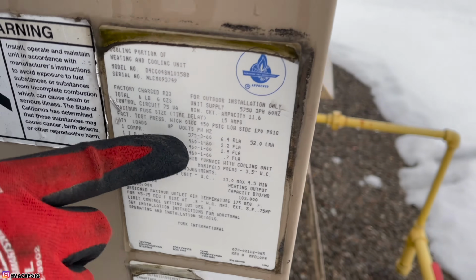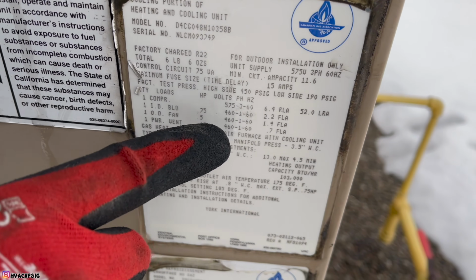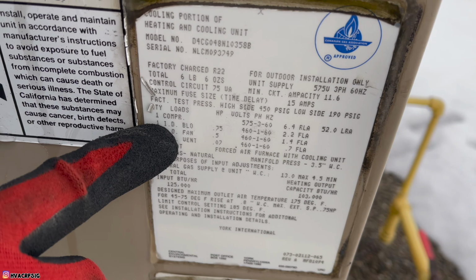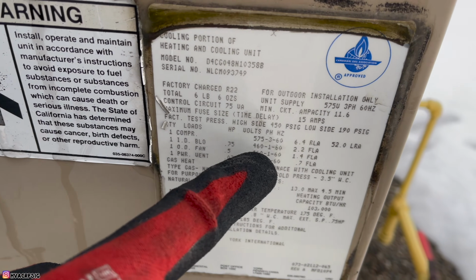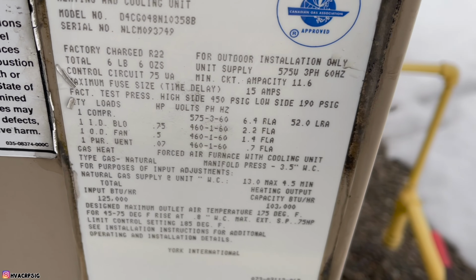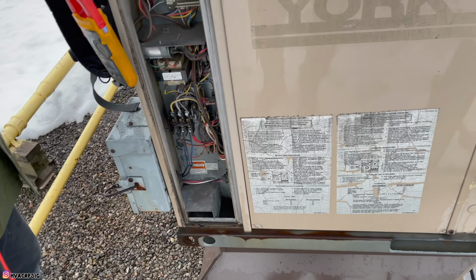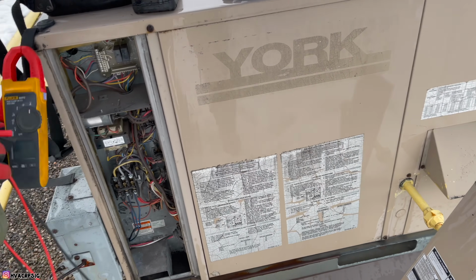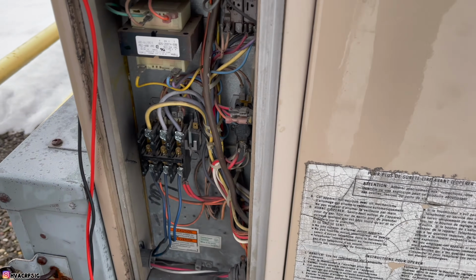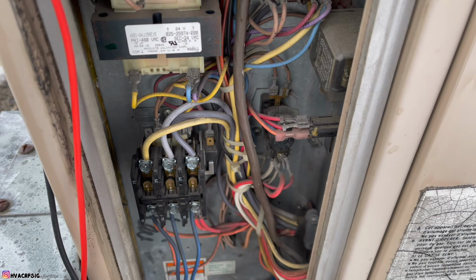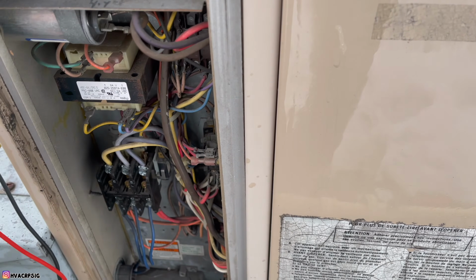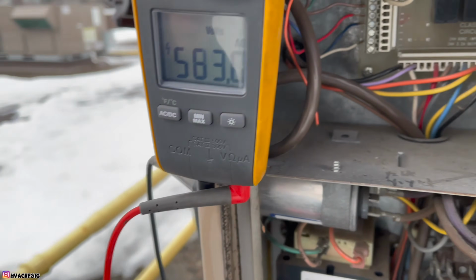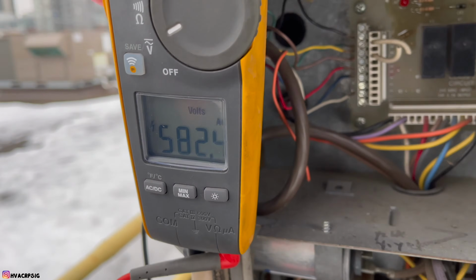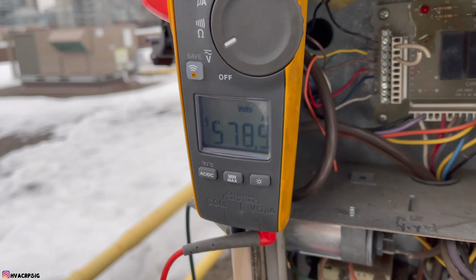Exactly. The compressor is 575 3-phase, but the motor for the indoor fan, the indoor blower, is 460 single phase, which is the other motor that we had. That's right. So again, with this unit, guys, the thermostat was blank. Check power on both sides. This unit even has a sequencer. Like the other unit had a little board, but here we got an actual sequencer. Check the incoming power, which is these blue wires here on this side. So tell them what you're looking for. 600 volts, yeah.